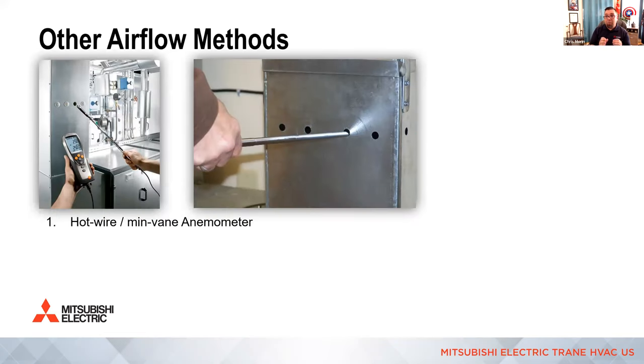There are approved ways of measuring volume of air. I personally, and Lisa, for commissioning purposes, is measuring external static pressure a good way to judge duct installation quality? Not by itself. That plus volume of air is a good way to judge duct installation quality.